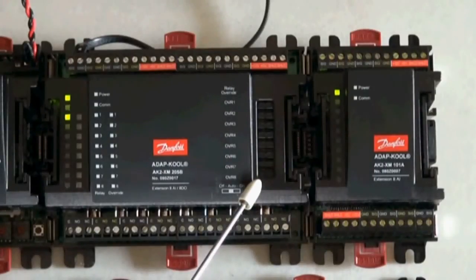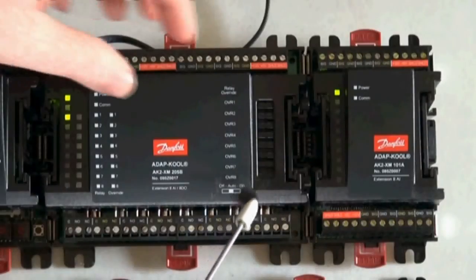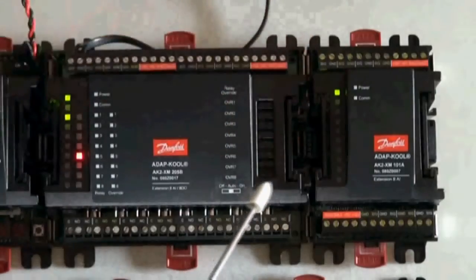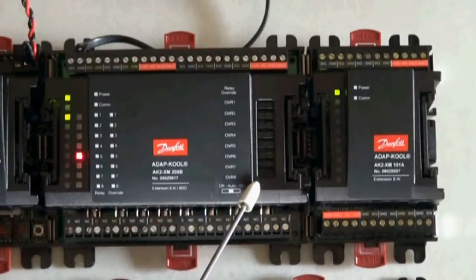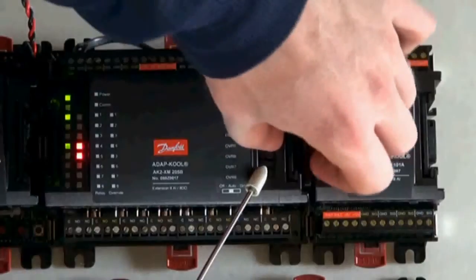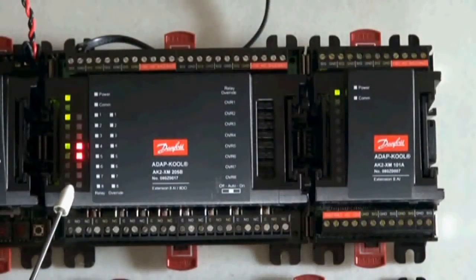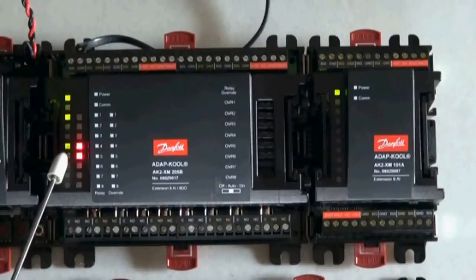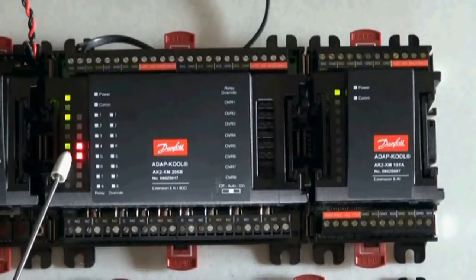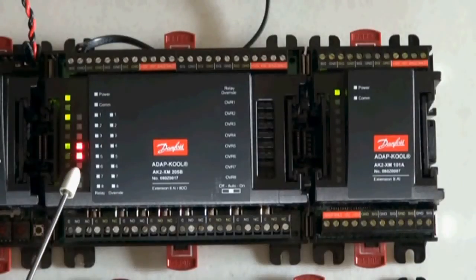Some modules may be equipped with recessed override switches. To override a load, simply move the switch to the left or the right depending on whether the load should be turned on or off. When the load is turned on or off, indicator lights on this side will remind us that we are in override, and the green light will indicate whether the relay coil is energized or de-energized. Right now, our indicator lights tell us that relay number 4 is in override and the relay coil is energized. Relay number 5 is in override, but the relay coil is de-energized.